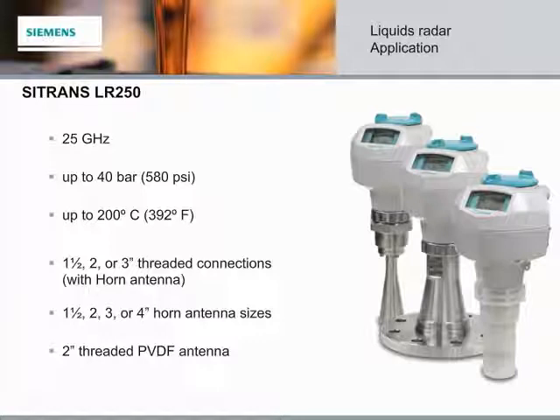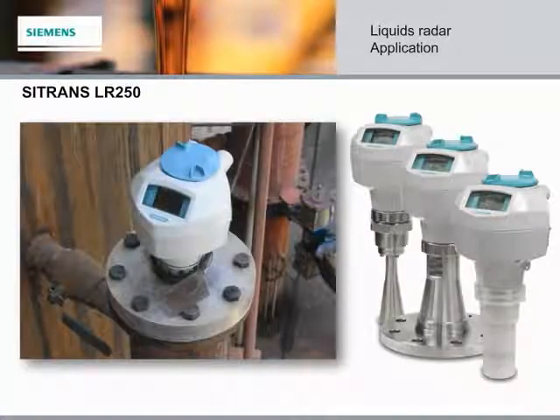Here is the SITRANS LR250, the ideal first choice in 90% of applications. It has a threaded PVDF and horned antenna option. It's a two-wire, 25 GHz pulse radar level transmitter for continuous monitoring of liquids and slurries in storage and process vessels. The 25 GHz frequency creates a narrow focused beam, allowing for small horn antenna options and decreasing sensitivity to obstructions. The SITRANS LR250 measures superbly on low dielectric media and in small vessels, as well as tall and narrow vessels.